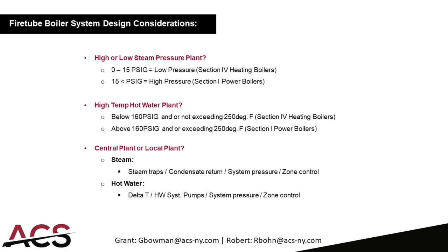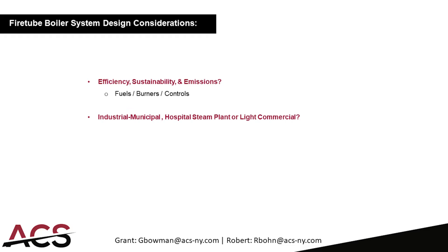For hot water systems, pay attention to delta T — hot water going out and returning — and the efficiency related to that, your hot water system distribution pumps, system pressure, and zone control valves for each building or zone. For efficiency, sustainability, and emissions, this is where you get into the details of selecting boilers, burners, controls, and what kind of fuel you're using — natural gas, number two fuel oil, biofuel, or a renewable energy that could earn you RIN credits from the government.